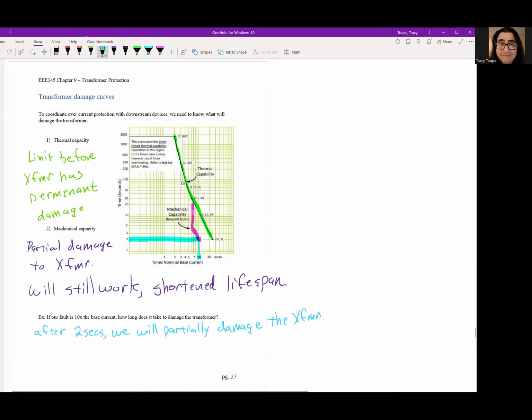So we hit it, it's bad, but let's say there's no protective device. We're going to keep on going. The current's still going to stay longer and longer. We're going to go up this page. We're going to eventually hit this point right here. And this is about right here. So once you hit that green line, that's bad news. And that's about 10 seconds. So nothing happens after 10 seconds, which is a long time, to be honest, right? Something cooking for 10 seconds is going to have permanent damage. We will have to replace the transformer, meaning it burnt down.